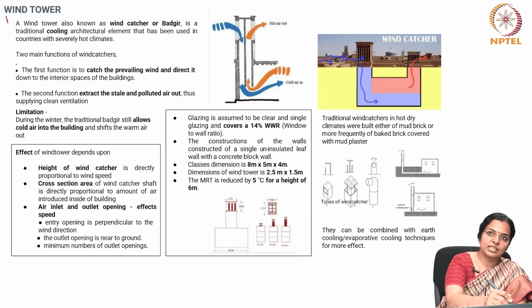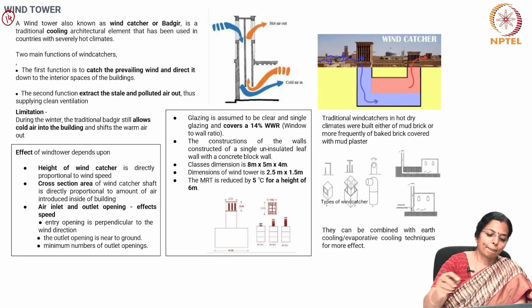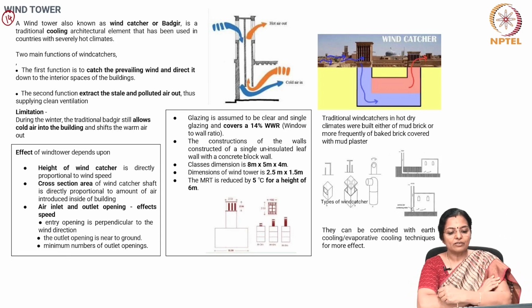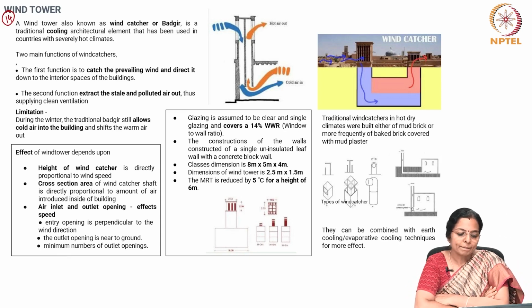Next strategy is the wind tower. The wind tower, also known as wind catcher or badgir, is a traditional cooling architectural element that has been used in countries which are severely hot. They have two main characteristics. The first function is to catch the prevailing wind and direct it down to the interior spaces of the buildings. The second function is to extract the stale and polluted air outside, thus supplying clean ventilation.